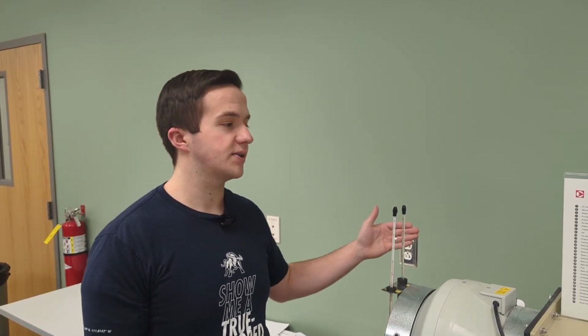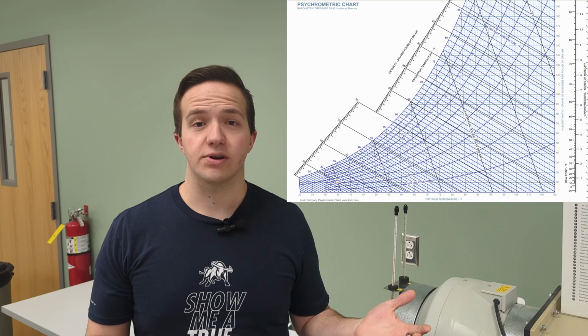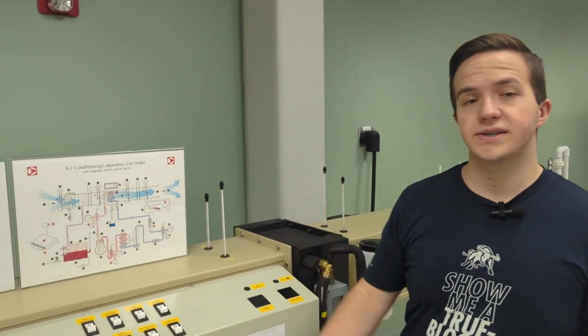Next, verify that both the wet and dry thermometers are functioning properly. The wet thermometers are located on the close side of the system, with the dry thermometers being located on the far side of the system. The wet and dry temperatures are used during analysis along with a psychrometric chart to calculate the enthalpy of the system.